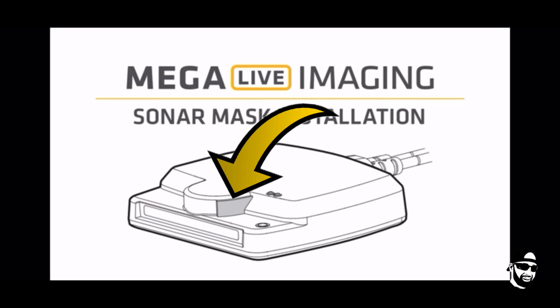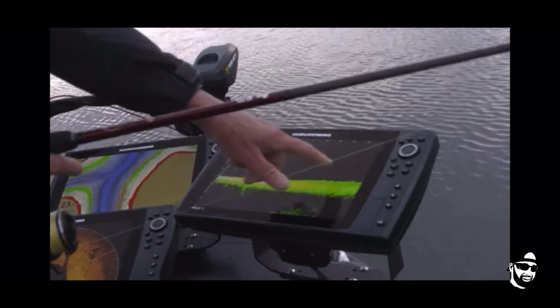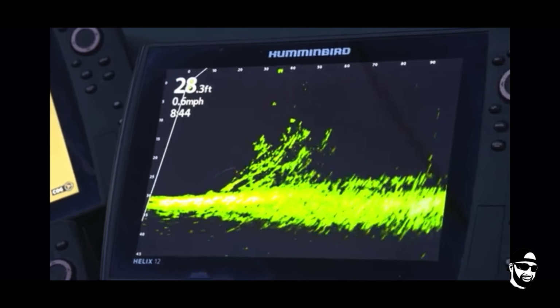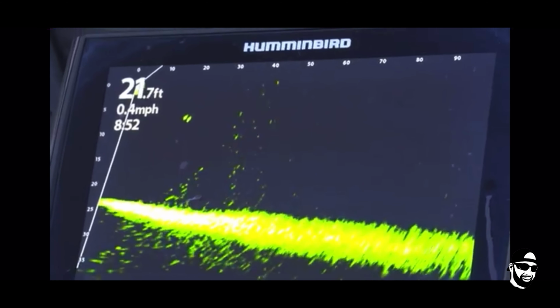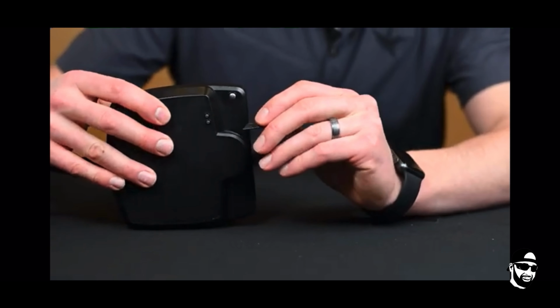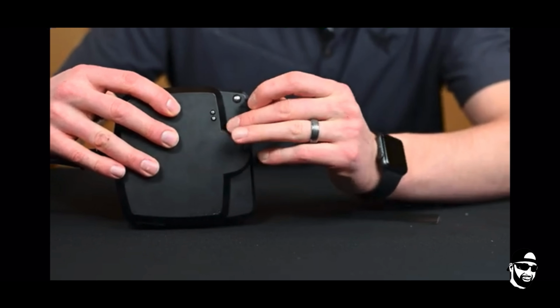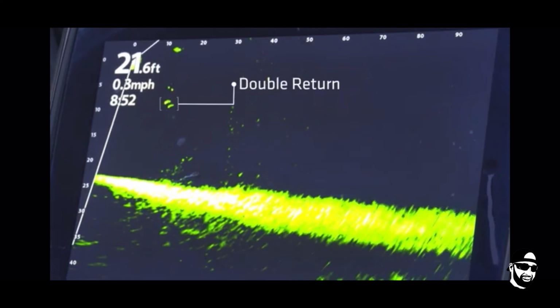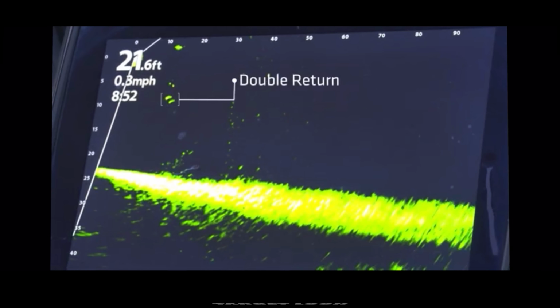All right, so moving over to MegaLive 1 double returns. Now, I know this was not mentioned during the product announcement, but I hope the newly designed MegaLive 2 has addressed this issue. The MegaLive 1 transducer needed some help with double returns, and the fix was placing a small piece of tape called a mask in a certain area of the transducer. I'm interested to know if MegaLive 2 will work without a mask, because as a customer, I have an issue with fixing a technology or hardware issue with a physical piece of tape. So hopefully they got this issue resolved and we can move forward.